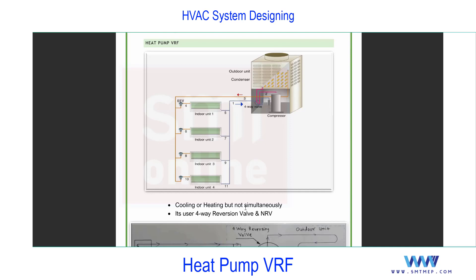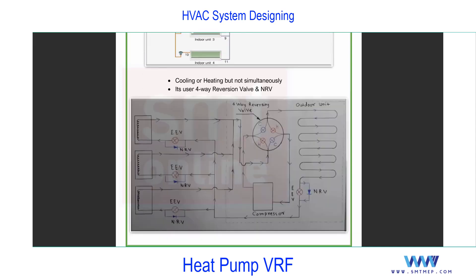Remember: heat pump VRF is for cooling or heating, but not simultaneously. This is important compared with the next heat recovery type. So you can use it only for cooling or only for heating for all the units, but not partly cooling or partly heating. The cycle can reverse, and it uses a four-way reversing valve and NRV.